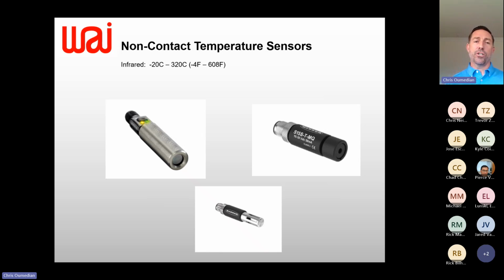Third portion of temperature sensing is non-contact. So contact, great. You need to be right in the media. Really, if you're trying to get the most accurate, you want to be in the media. There's some applications where that's just not a reality. You can't do that. There's no way to get to it. It's enclosed, whatever. You don't want to touch it. It's pharmaceutical, it's food. You don't want to have anything in that media that could grow bacteria, that could cause issues with the product. Then we would look at a non-contact temperature sensor.